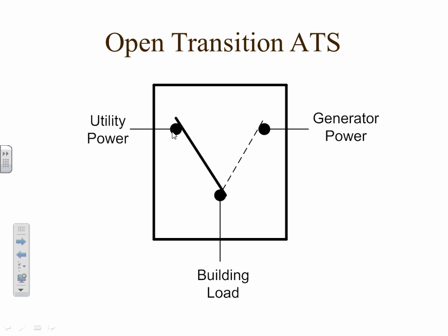Over a course of time, people were all different, you know, they come on gradually, this house, and half hour later this house, and businesses, you know, they've turned up their thermostats and got the air conditioning running. Now we've got all this air conditioning load on. It's an extremely hot day. What's the utility trying to do when we first retransfer back off? When the utility first comes back, if you imagine the control room, now the utility is trying to start all of these air conditioning systems online at the same time. You guys know enough about motor starting right now. You've been through the sizing program. What can you tell me about the starting of a motor? One motor.